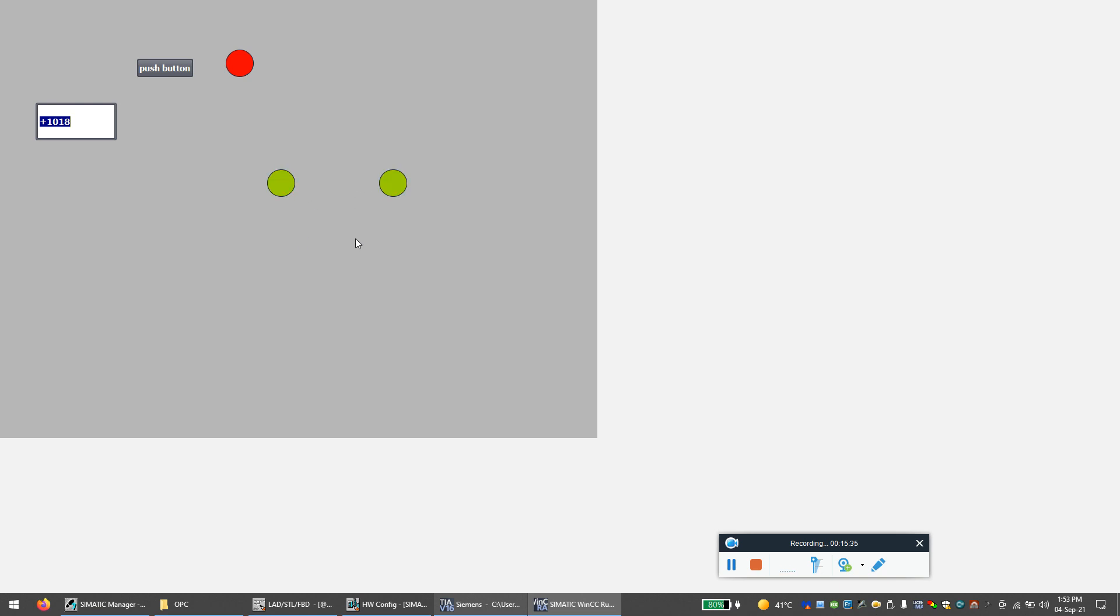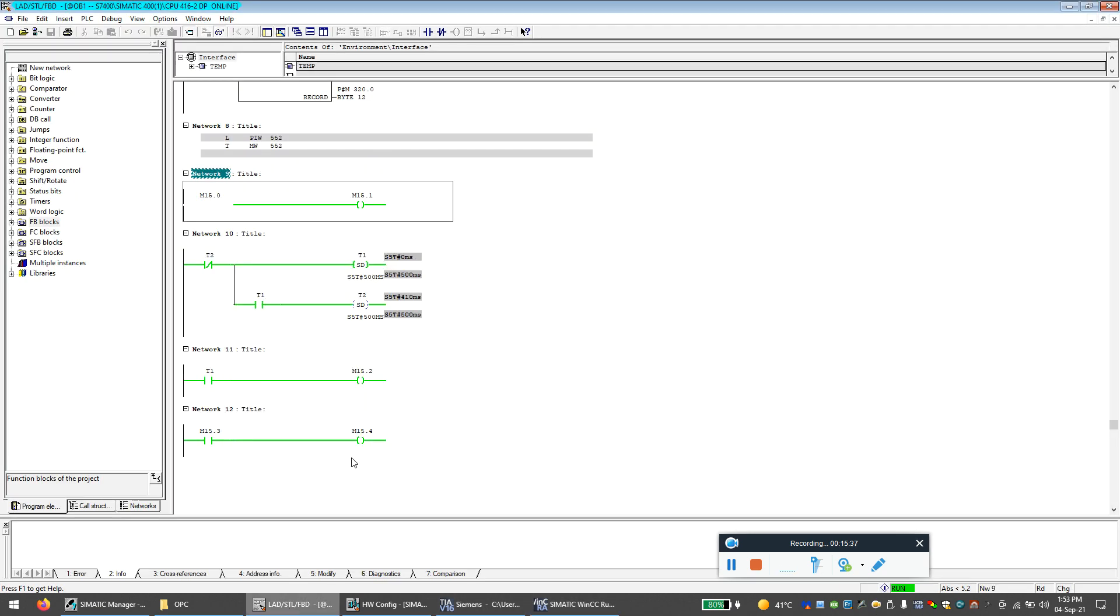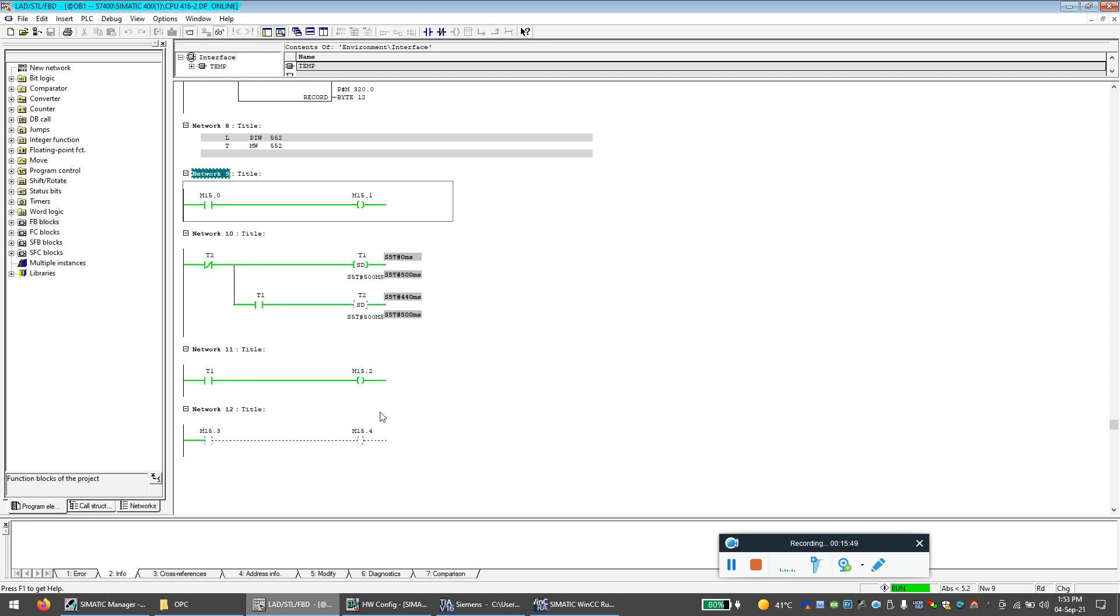Now it is working. So you can see what is the program. So when this bit is generated, it gets written to this bit from the SCADA. This bit will enable this. So by monitoring this bit, we can make sure that the SCADA is communicating with the PLC properly.